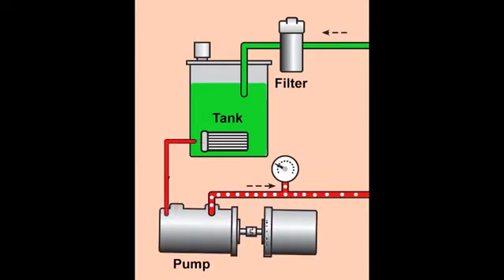Increasing the size of the inlet line or reducing flow can help with cavitation problems. Removing any elbows, bends, or filters on the inlet line can also help. Lastly, make sure that your oil reservoir is above the pump.